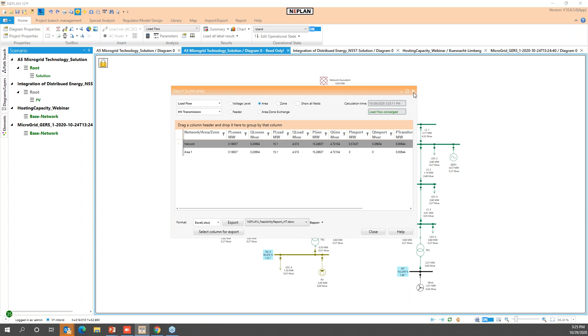If you remember, connected to the system, the losses are now, let's see, 0.18, a bit higher than when the system was connected entirely, which is, I would say, expected, of course. We are now running with the system disconnected from the main grid, but still, the losses are lower than those that happen when the system doesn't have any renewable or other generating source. What does this show? That, yes, of course, a very well planned microgrid can work perfectly.